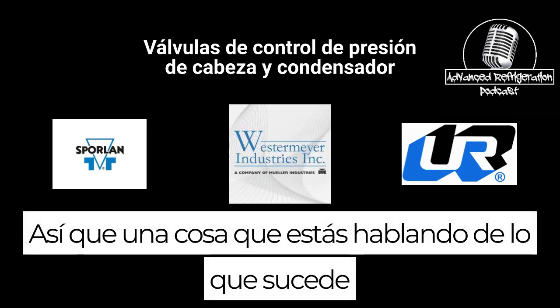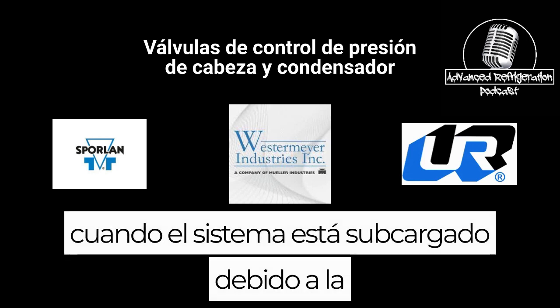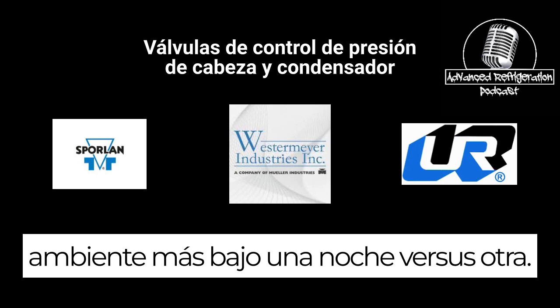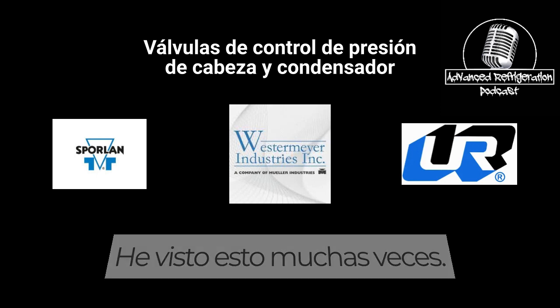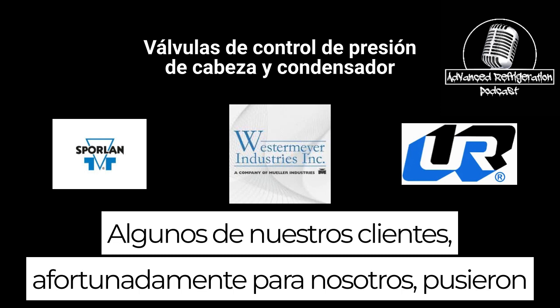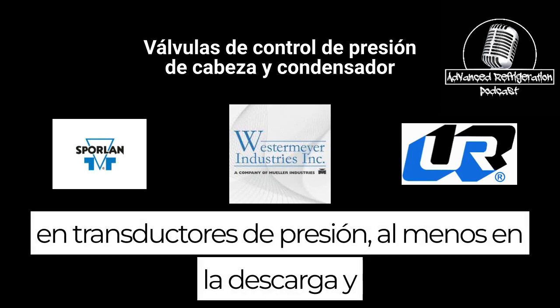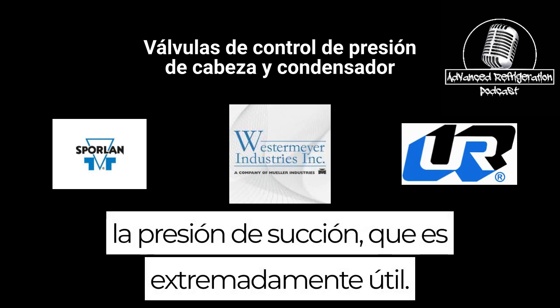Yeah, I do actually. So one thing, you're talking about what happens when the system's undercharged due to the lower ambient one night versus another. Well, I've seen this many a time. Some of our customers, fortunately for us, put on pressure transducers at least on the discharge and the suction pressure, which is extremely helpful.